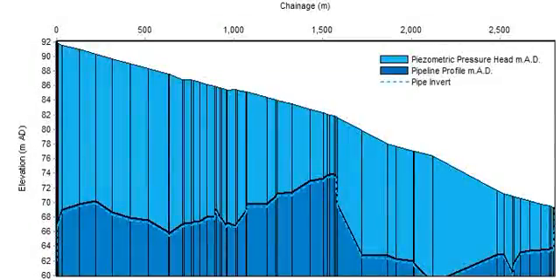Hi, I'm Peter Glover and we're looking at the pump stop scenario. When a pump stops, the fluid downstream of the pump carries on moving as if nothing had happened. It takes time for the force, the pressure drop, to propagate along the pipeline, and this can lead to some very unfortunate events.